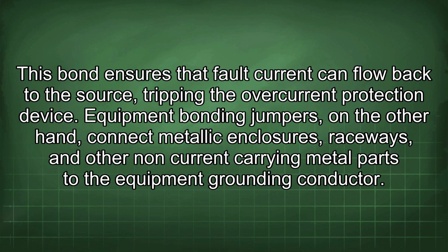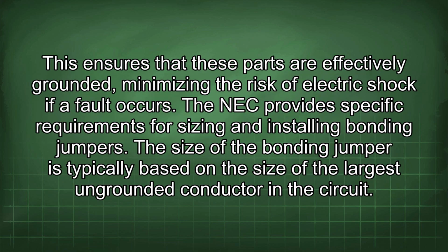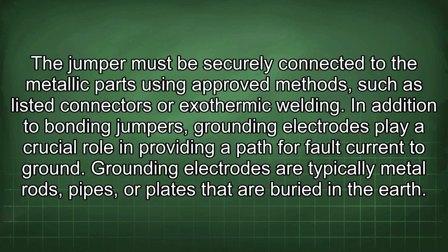Equipment bonding jumpers, on the other hand, connect metallic enclosures, raceways, and other non-current carrying metal parts to the equipment grounding conductor. This ensures that these parts are effectively grounded, minimizing the risk of electric shock if a fault occurs. The NEC provides specific requirements for sizing and installing bonding jumpers. The size of the bonding jumper is typically based on the size of the largest ungrounded conductor in the circuit. The jumper must be securely connected to the metallic parts using approved methods, such as listed connectors or exothermic welding.